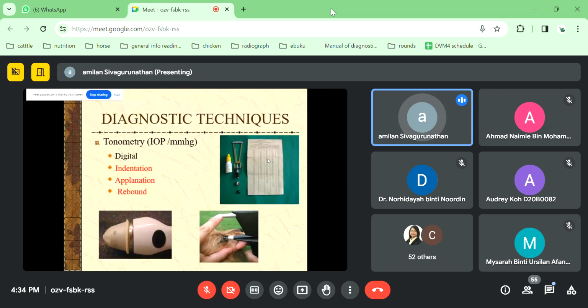Other than the visual inspection that we talked about earlier for the acute and chronic signs, we also have tools to measure. The instrument on the far top is called the Schiotz tonometer, and this is a traditional way of measuring pressure. I don't believe they sell them anymore, but the weight is applied on this scale, and the patient is positioned with the head upright, and the scale is dropped on the cornea gently, and the measurement is taken there. So that's called an indentation tonometer.